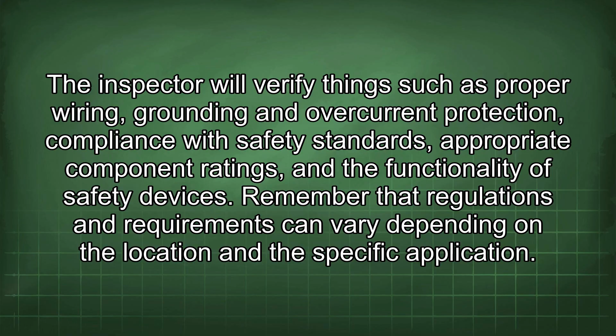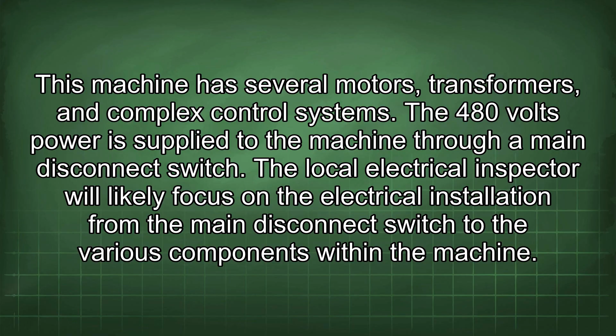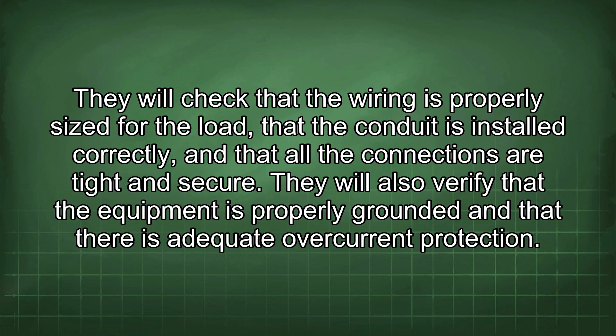Now let's consider some specific scenarios and how the relevant codes and standards might apply. Imagine a large industrial machine used in a manufacturing plant. This machine has several motors, transformers, and complex control systems. The 480 volts power is supplied to the machine through a main disconnect switch. The local electrical inspector will likely focus on the electrical installation from the main disconnect switch to the various components within the machine. They will check that the wiring is properly sized for the load, that the conduit is installed correctly and that all the connections are tight and secure. They will also verify that the equipment is properly grounded and that there is adequate overcurrent protection.